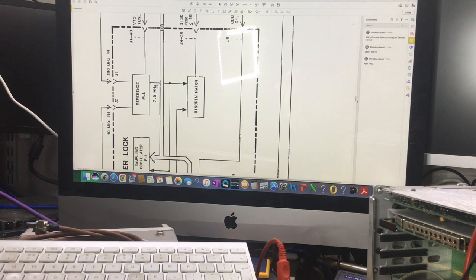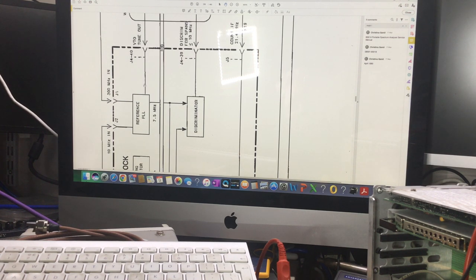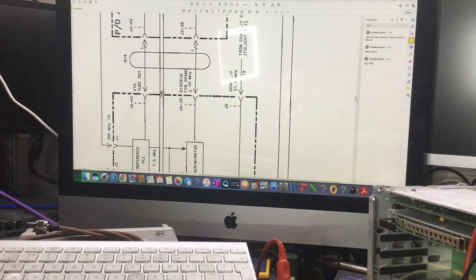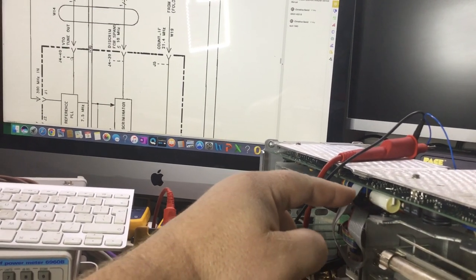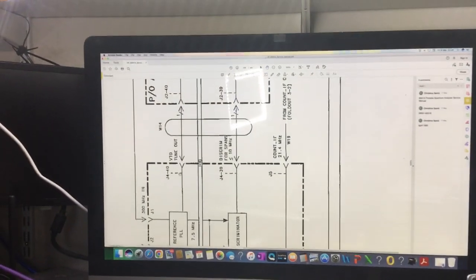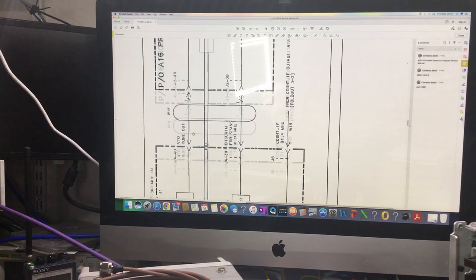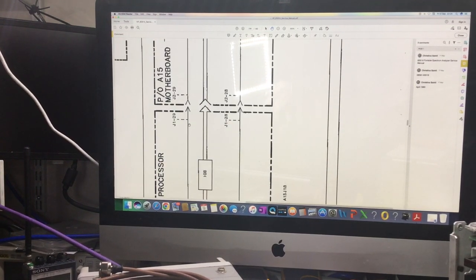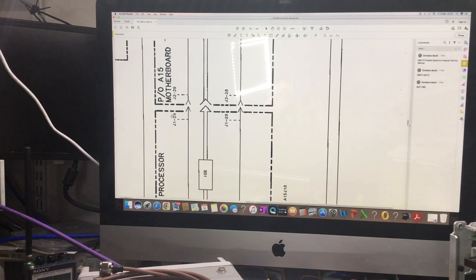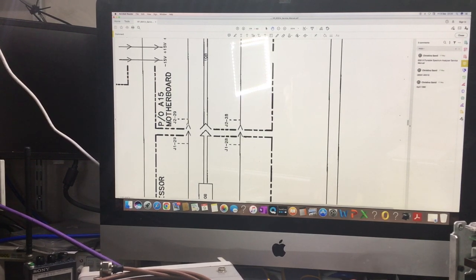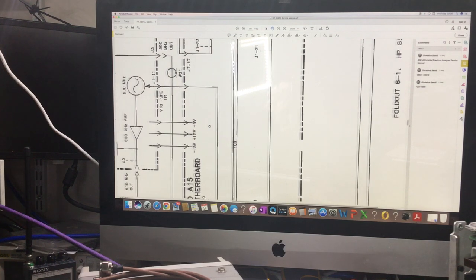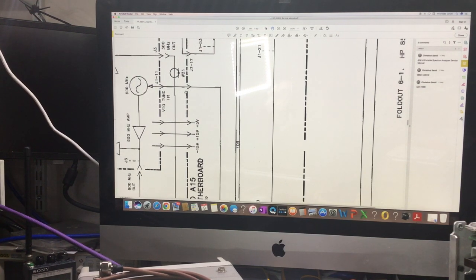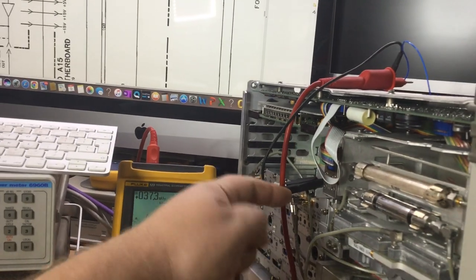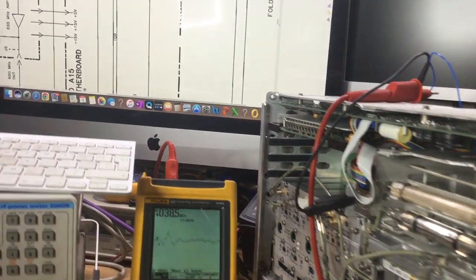So it could be that it's outputting those signals, as it should be, but the actual control volts line goes through from J4, which is on the top of the control board, the processor board. It goes through J4 and enters the top of the processor board, and then comes out on J1, which is underneath pin 29, which is where we're soldered to, enters J2, which is the other socket I showed you that's blue, and then from there it goes into the motherboard section, comes out of the motherboard on the sockets underneath these modules here, the sockets down there on the motherboard that these modules plug into.